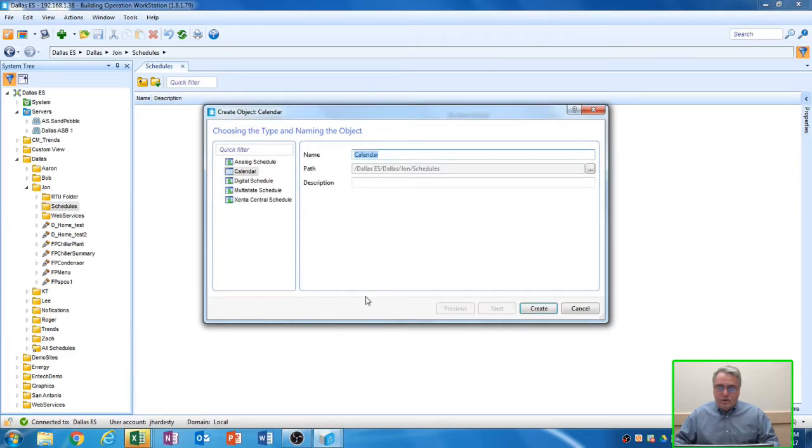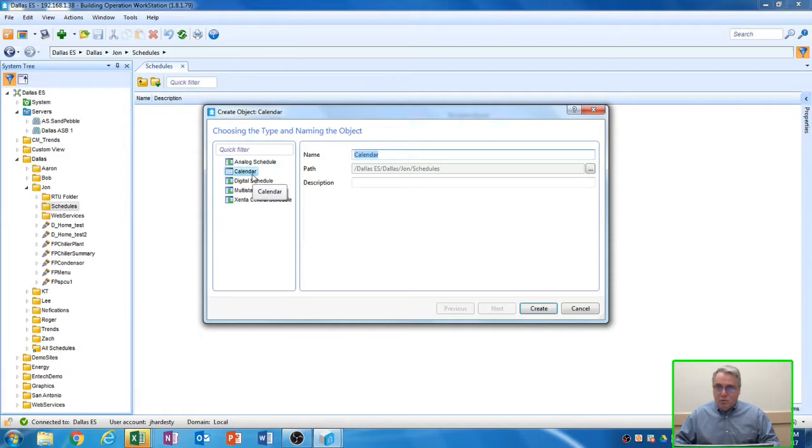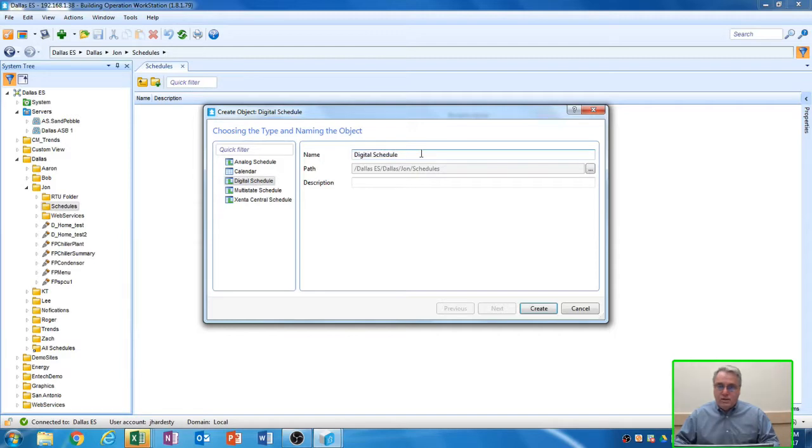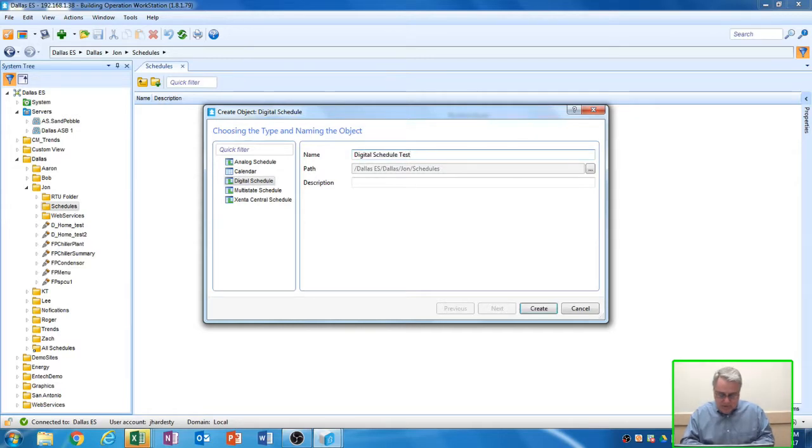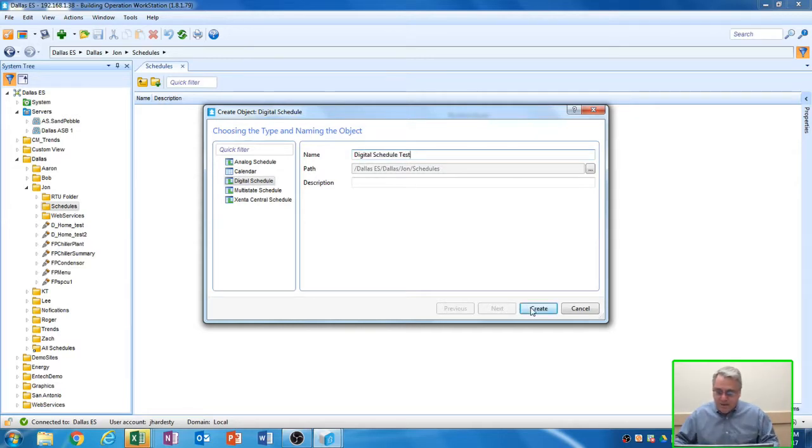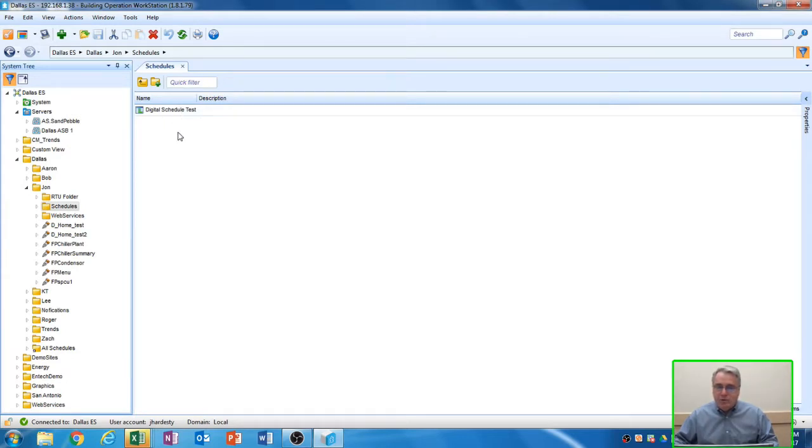And when I do, it asks you to choose the type of schedule and the name for the schedule. There are multiple types of schedules that you can select. Analog schedule, calendar for holidays and such. We're interested in a digital schedule because we want to turn the piece of equipment either on or off. So I'm going to call this Digital Schedule Test and select the Create button, and you'll notice now there's a schedule listed in my folder here.